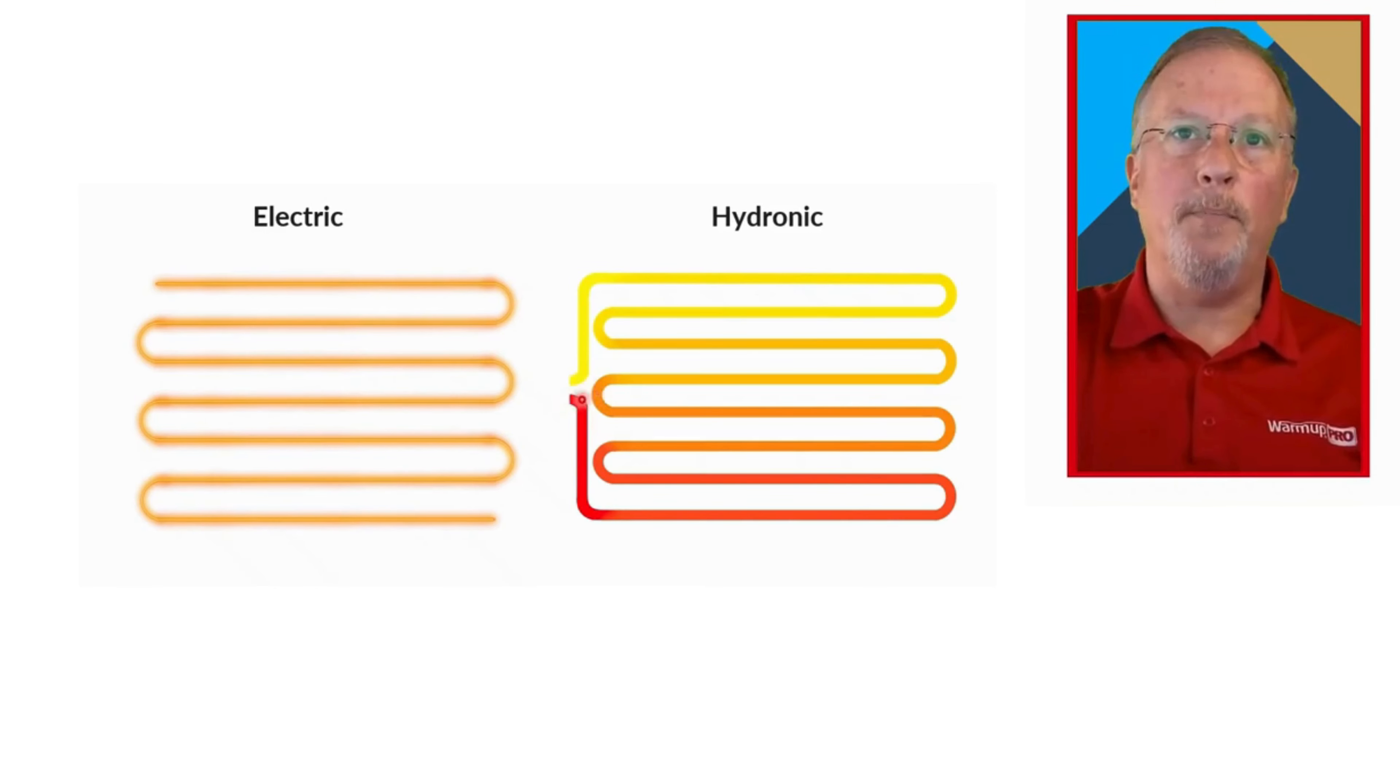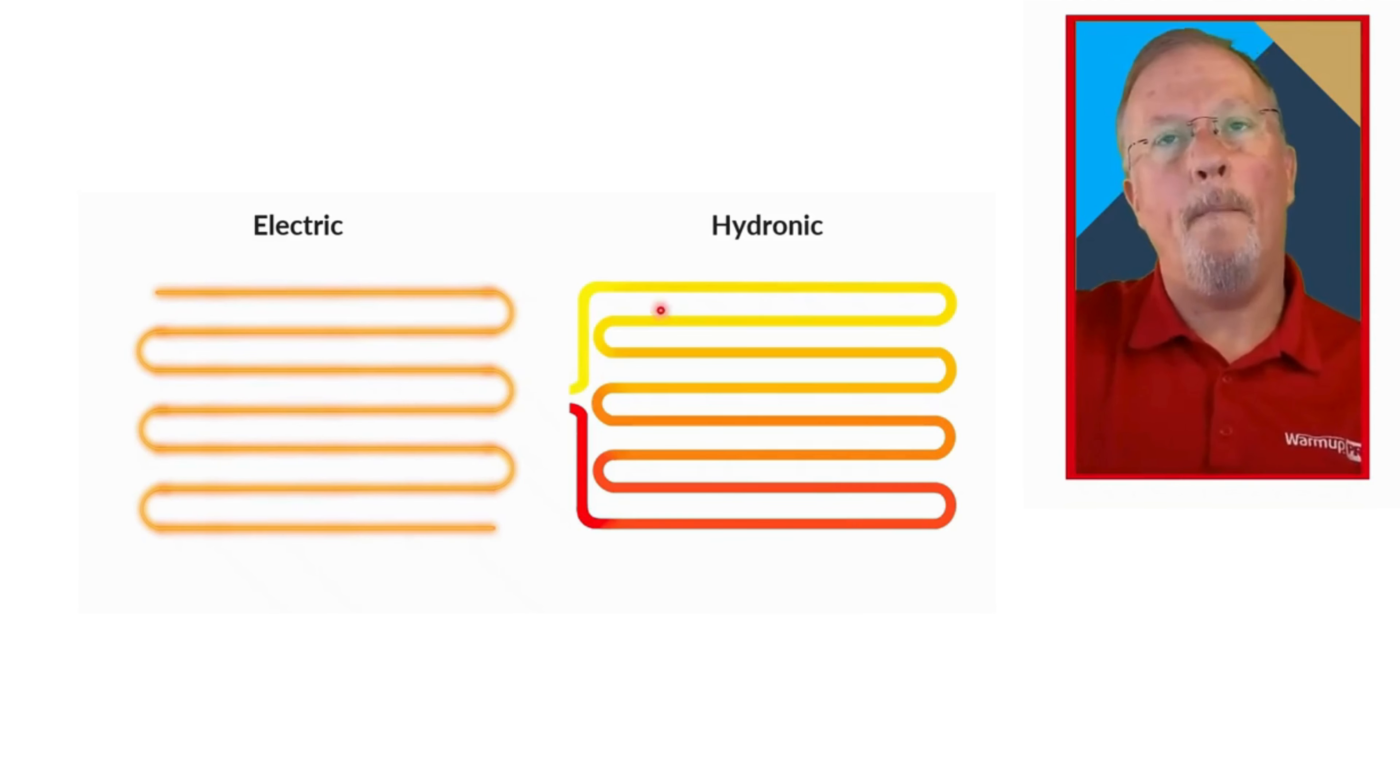The temperature difference between where it comes in and where it goes out could be 20 degrees or thereabouts. Although still much better than a forced air system, because we're heating the entire floor, the difference between the electric and the hydronic system mainly is because the electric side heats the floor perfectly on every inch of the cable, because it has the exact same amount of output.